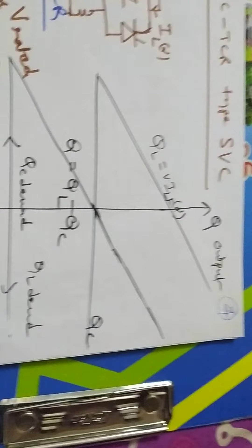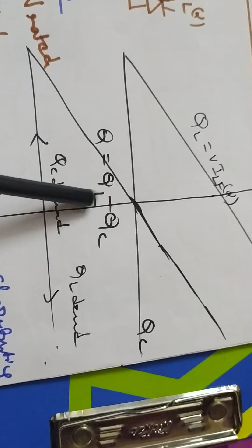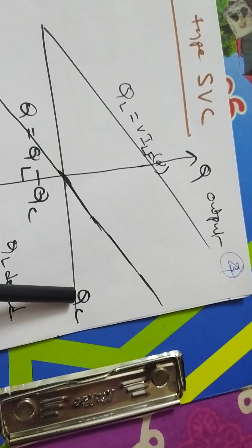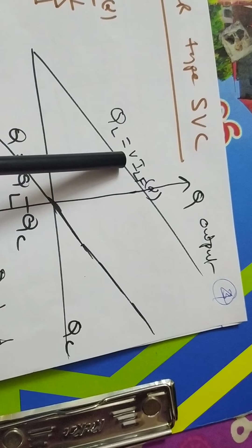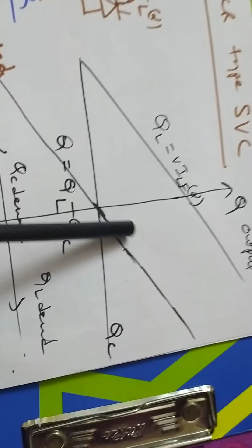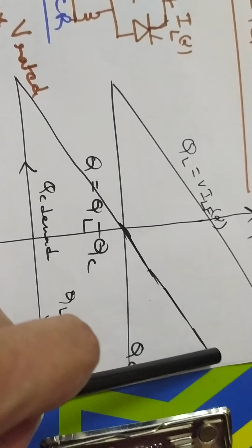Coming to the VI characteristics of SVC. This is the QL demand, QC demand on the x-axis. The y-axis is reactive power supplied by the SVC, and this is the QC, fixed reactive power compensation by the FC, and this is the QL, a function of IL(alpha) into V supply voltage. The summation of these two gives you the exact reactive power. Q is equal to QL minus QC, the reactive power supplied by the SVC.